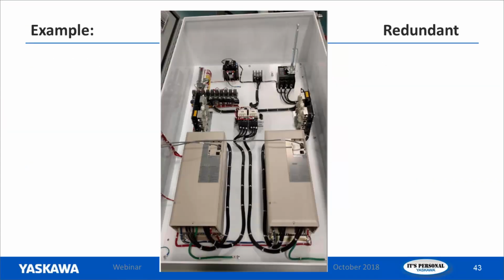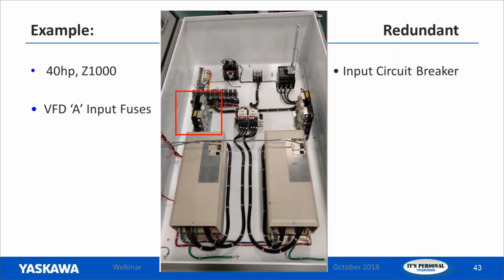We'll take a look inside of this. In this example, we've got two 40 horsepower Z1000 drives. In this example, it's a circuit breaker rather than a disconnect switch. So here we have our input circuit breaker. And we've got our input fuses for drive A, and we've got our input fuses for drive B.